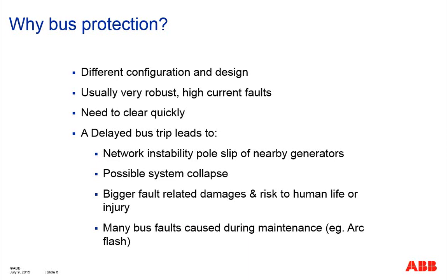But nowadays, with power system equipment being operated really near their rated limitations, and the increased short circuit level and therefore the impact on system stability, busbar protection has really become a requirement for modern substation, especially high voltage and extra high voltage substation protection design.